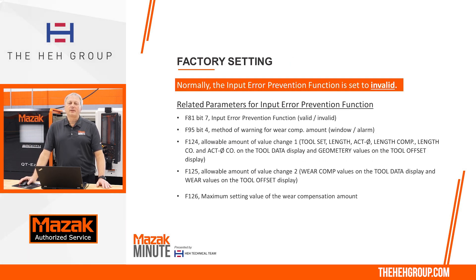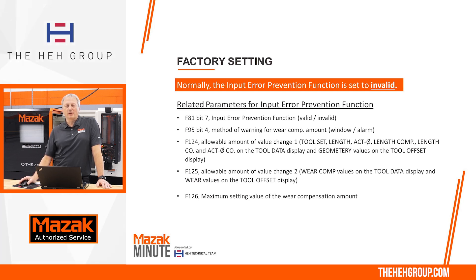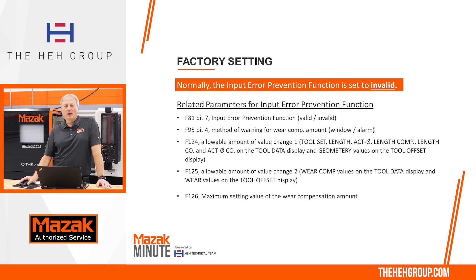Normally, the input prevention function is invalid from the factory. Parameter F81, bit 7 is the parameter that will validate it. F95, bit 4 gives the ability to have a window appear on screen if the increment value is larger than a predetermined parameter. F124, F125, and F126 are the parameters used for the maximum allowance.